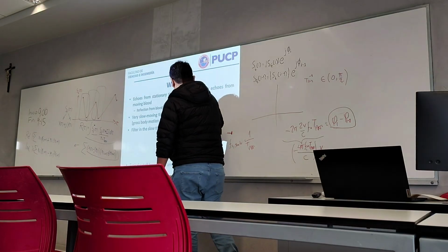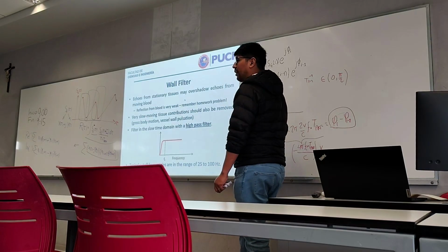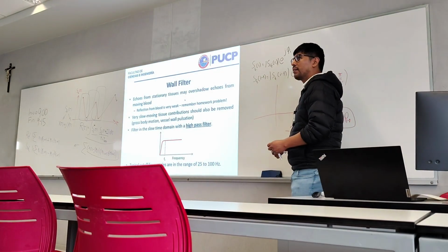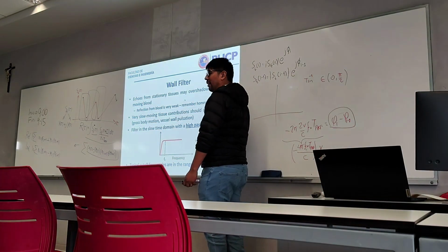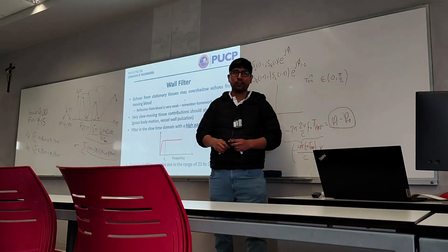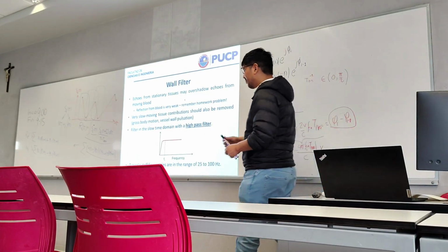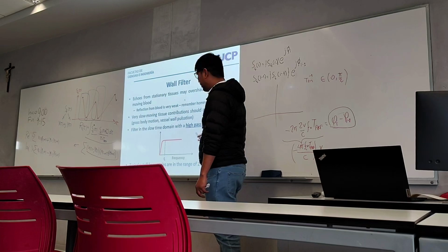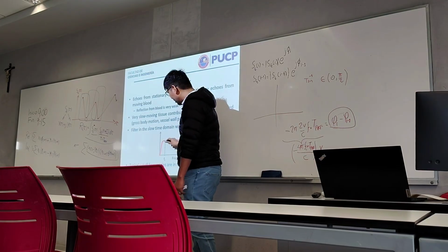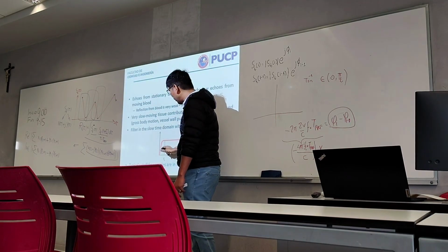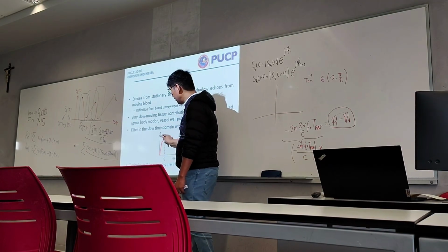And I was mentioning before, the static tissues, the tissues that are not moving, that signal needs to be cancelled. And to cancel the signal with zero frequency, a filter is applied. In this case, a high pass filter. A filter that keeps only frequencies above some cutoff frequency. Basically this high pass tries to eliminate all the low frequencies, and especially the zero frequency.